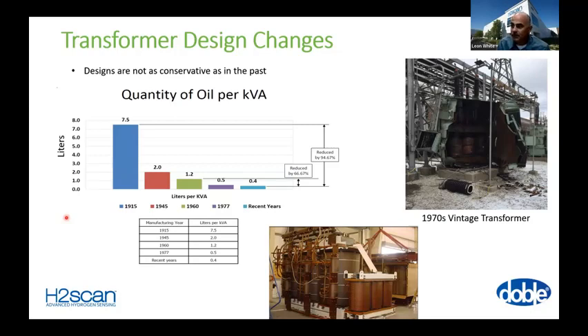But the story behind this transformer was apparently they had some large motors that needed two transformers to start up, and one transformer was out of service. So they found out the hard way that you really can't start the big motor with one transformer. I had never seen a transformer open up the tank like a door, so I found that to be a very interesting case. And then I'll let Tony talk about the complexities of some of the transformers today on the picture down below.